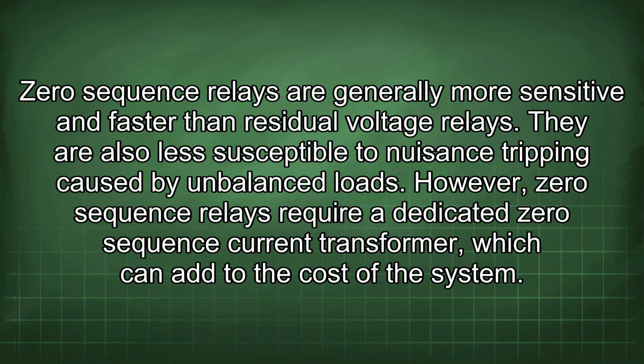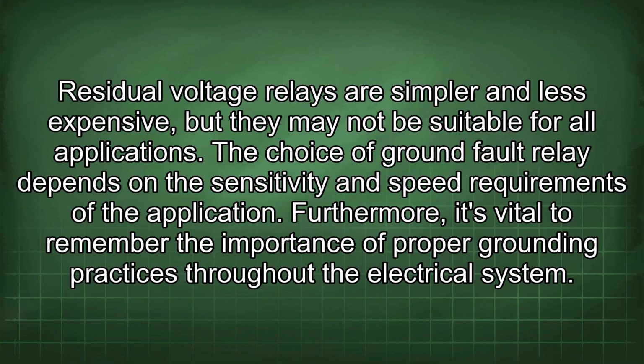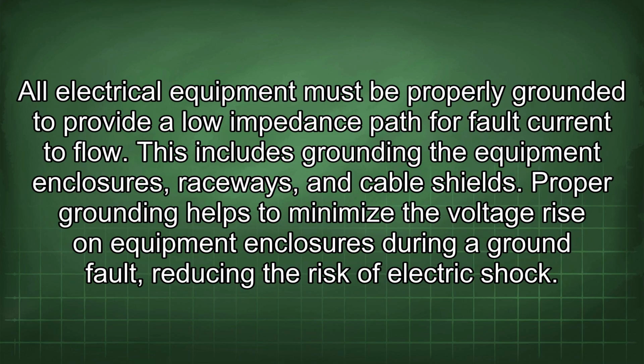Zero-sequence relays are generally more sensitive and faster than residual voltage relays. They are also less susceptible to nuisance tripping caused by unbalanced loads. However, zero-sequence relays require a dedicated zero-sequence current transformer, which can add to the cost of the system. Residual voltage relays are simpler and less expensive, but they may not be suitable for all applications. The choice of ground fault relay depends on the sensitivity and speed requirements of the application. Furthermore, it's vital to remember the importance of proper grounding practices throughout the electrical system. All electrical equipment must be properly grounded to provide a low impedance path for fault current flow.